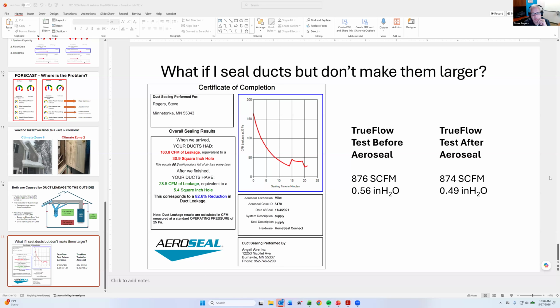To answer the other question, I saw that, and if I'm going to share my screen here very briefly, Sydney brought up a good question that I have heard a couple of times, and that is, if I seal my ducts, is my static pressure going to go up? Is my duct capacity going to go down? And I have one very well documented data point on that, which is not great. Nobody wants to work on one data point, but I always say one data point is better than zero. So technically, yes, if you seal ducts, the static pressure should go up and the capacity that you can move through them should go down. But I think, based on the one data point that I'm going to show you, the answer is it's probably a lot less than you think.